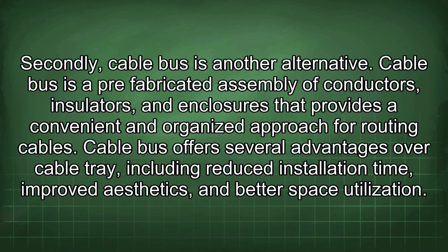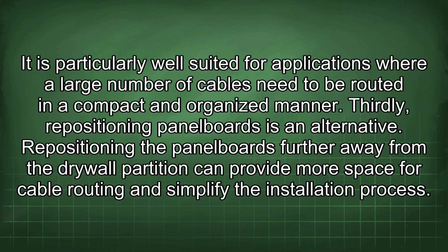Secondly, cable bus is another alternative. Cable bus is a prefabricated assembly of conductors, insulators, and enclosures that provides a convenient and organized approach for routing cables. Cable bus offers several advantages over cable tray, including reduced installation time, improved aesthetics, and better space utilization. It is particularly well suited for applications where a large number of cables need to be routed in a compact and organized manner.